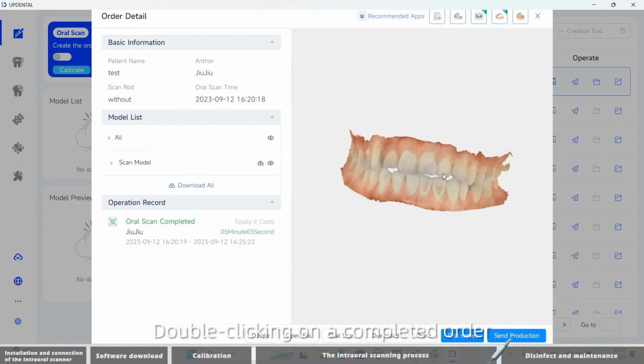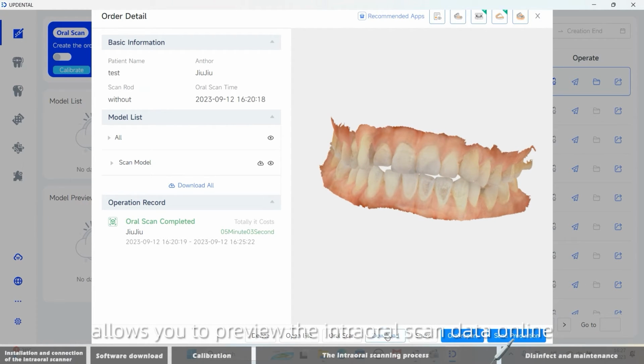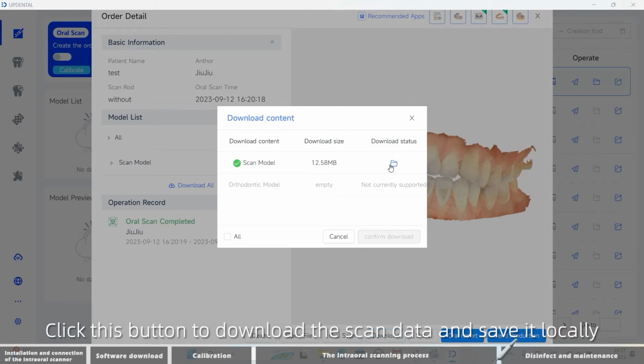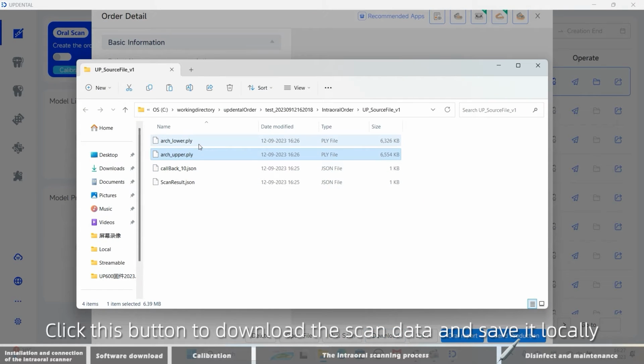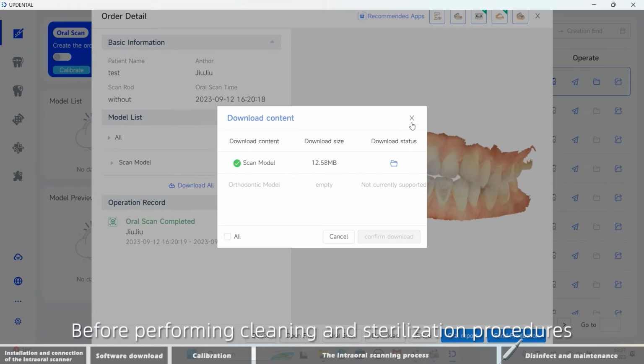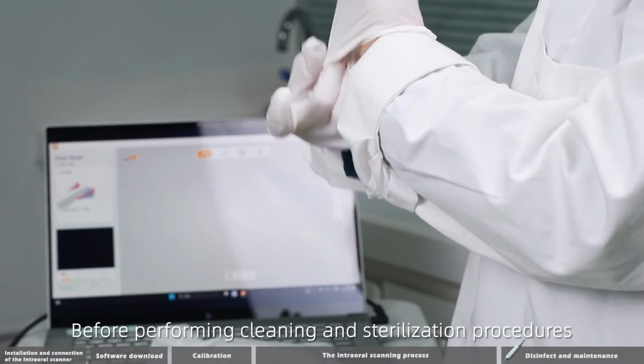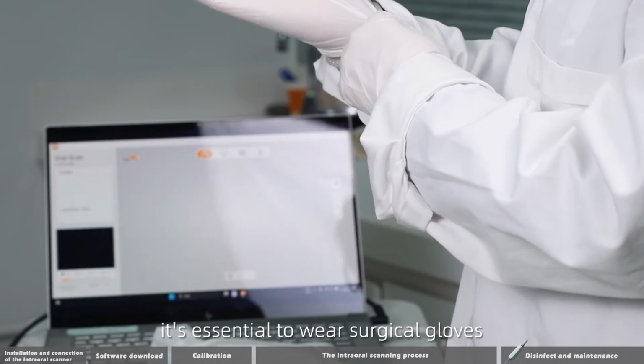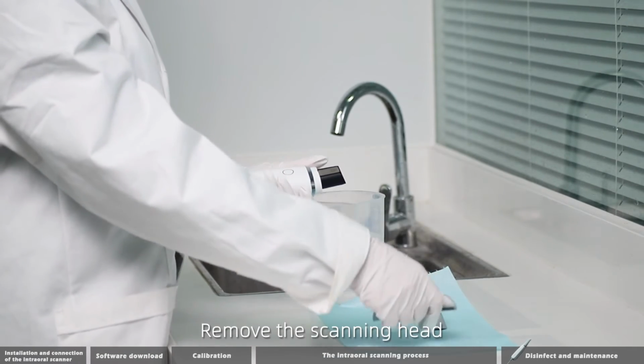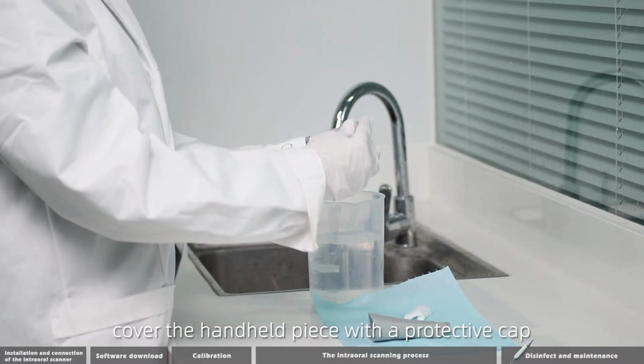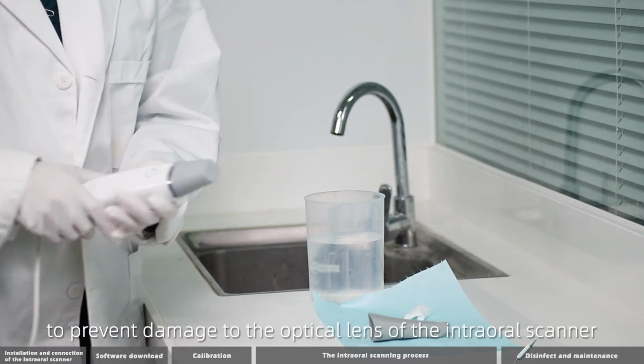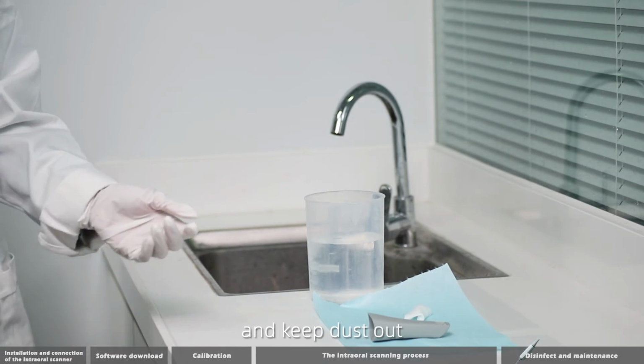Double-clicking on a completed order allows you to preview the intraoral scan data online. Click this button to download the scan data and save it locally. Before performing cleaning and sterilization procedures, it's essential to wear surgical gloves. Remove the scanning head. Cover the handheld piece with a protective cap to prevent damage to the optical lens of the intraoral scanner and keep dust out.